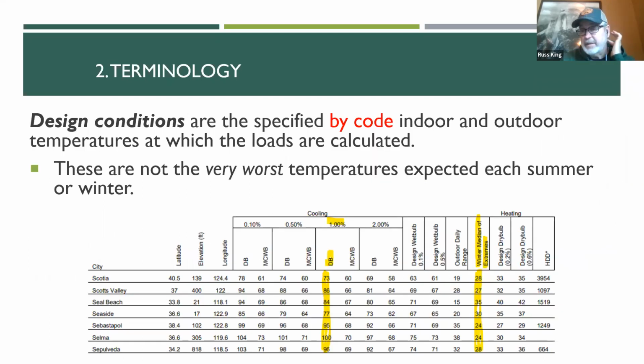Now, design conditions are specified by code. You're not supposed to mess around with those, okay? But contractors have a bad habit of doing that. You're supposed to use the design temperature specified by code, and they're picked for a reason. And there's temperatures for the inside of the house, and there's temperatures for the outside of the house. And then there's summer design temperatures and winter design temperatures, okay?